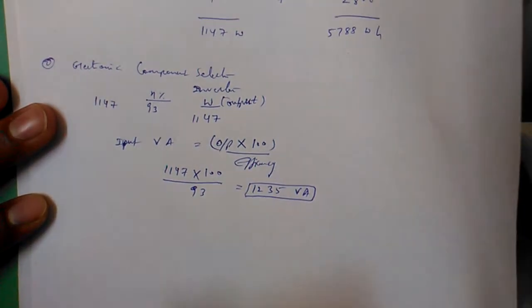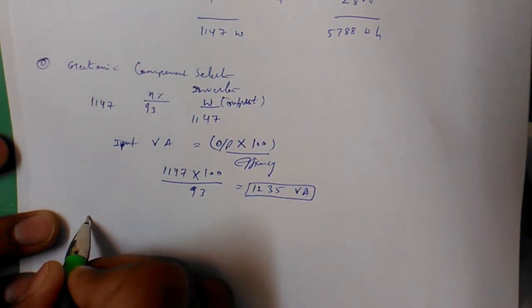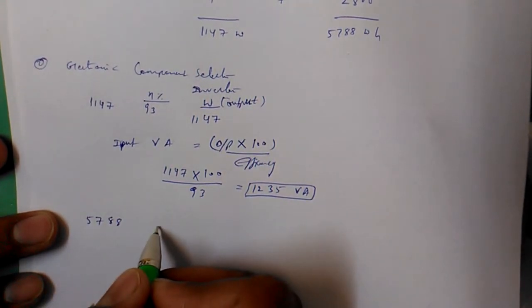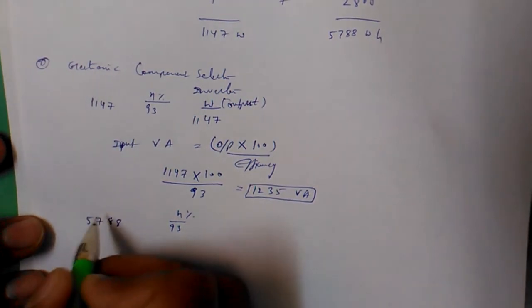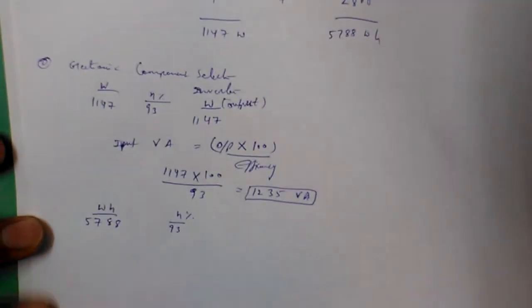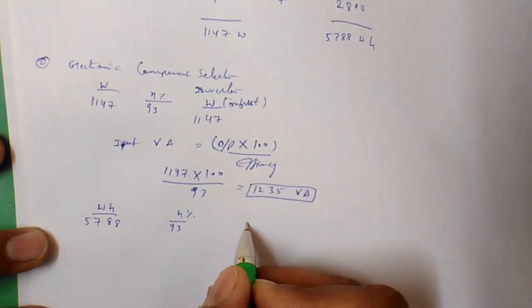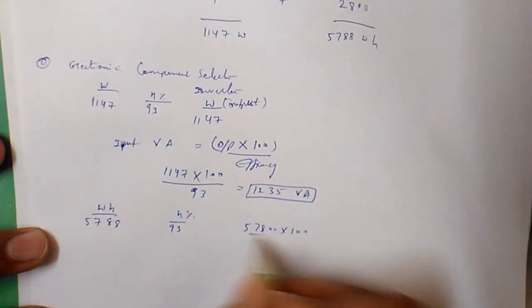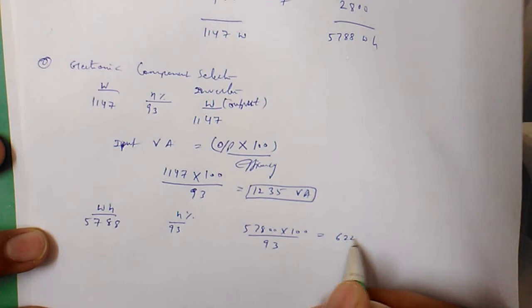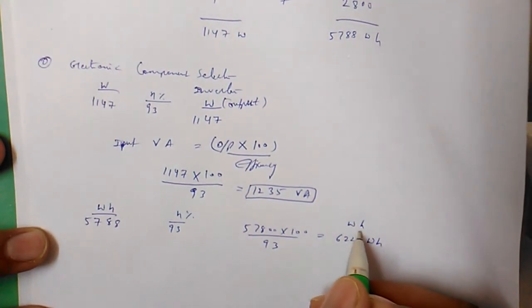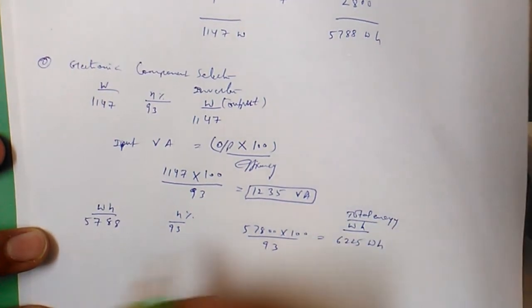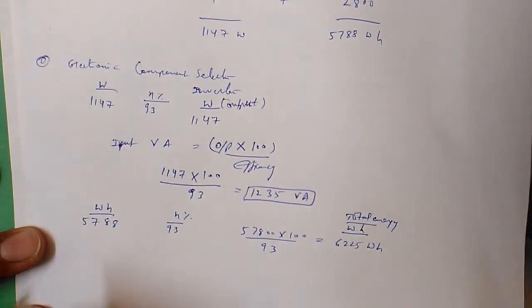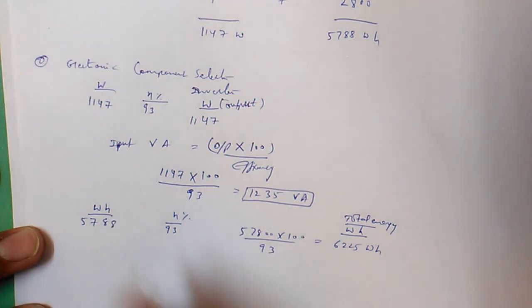Total energy is 5788 watt-hours and inverter efficiency is 93%. So energy input = 5788 × 100 / 93 = 6225 watt-hours. This gives us the corrected total energy accounting for inverter losses.